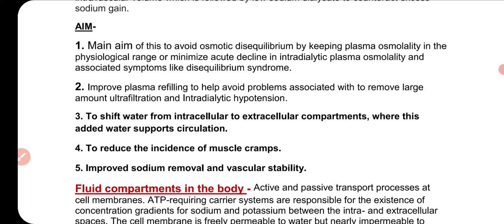To set this up, each machine has its own settings — some machines have a sodium range starting at 135. We have to set the profile for a specific time and a specific volume. For example, for a 4-hour session, if someone has problems during normal dialysis, we can do 3 liters of profiling.